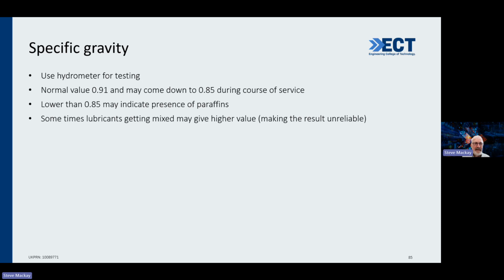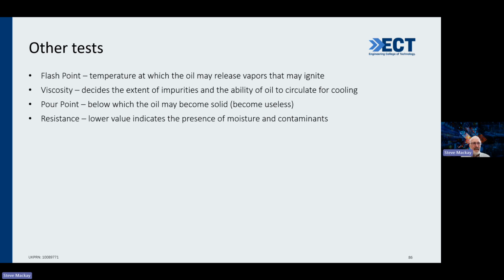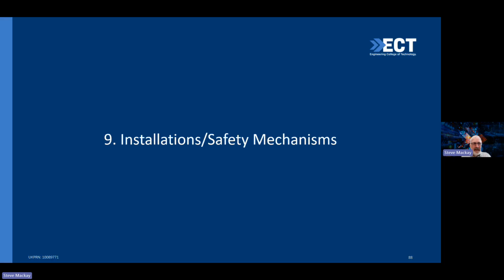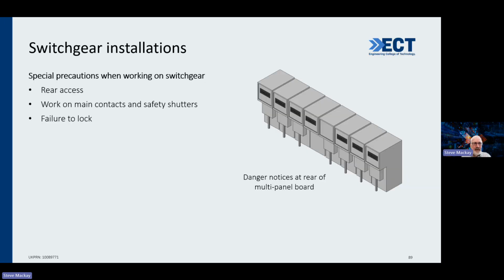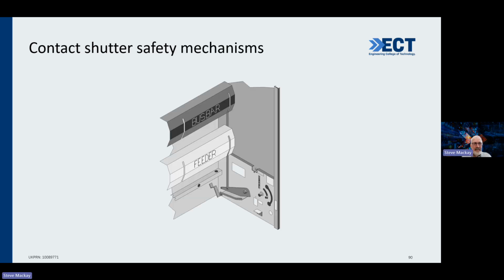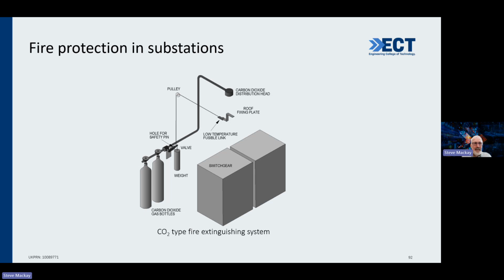Obviously, specific gravity is another test. Use a hydrometer for testing. Really important. Other tests are the flash point, viscosity, pour point, and resistance. So if the oil is at a low value, you know there's probably moisture or other contaminants in it. So those are all really important to look for. And here's a typical testing thing. So installation, switchgear installations, obviously rear access, work on main contacts and safety, failure to lock, phasing out. Fire protection in substations is another long, big issue here.